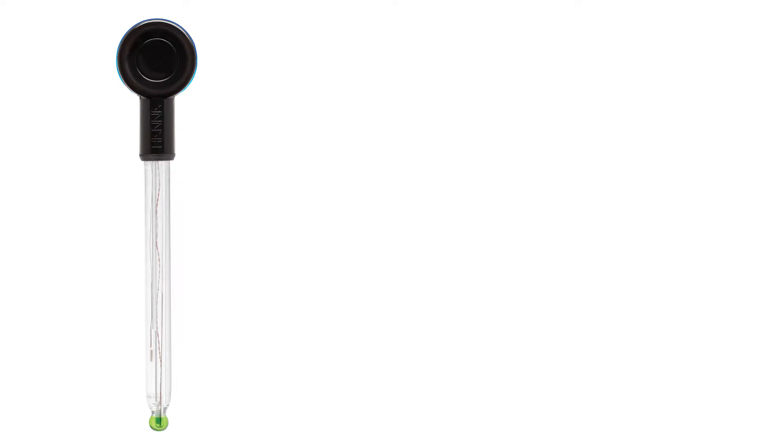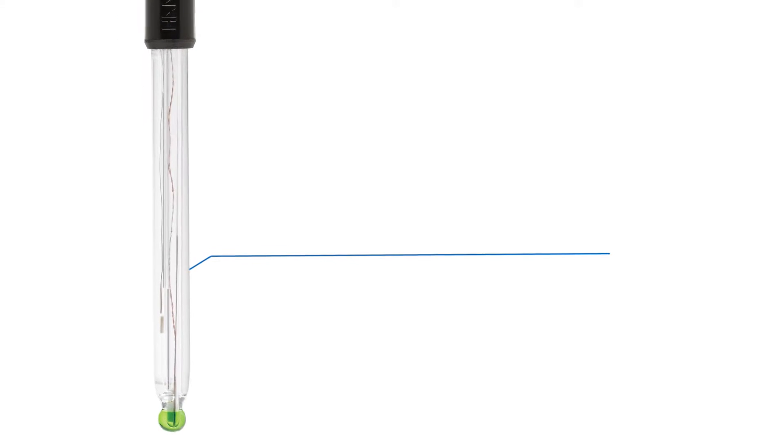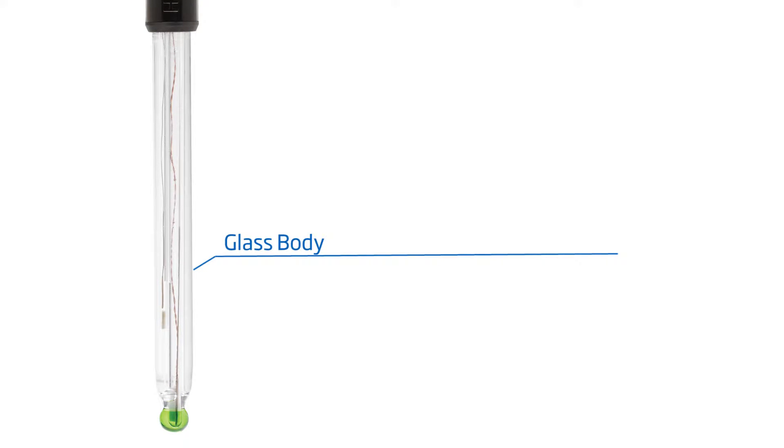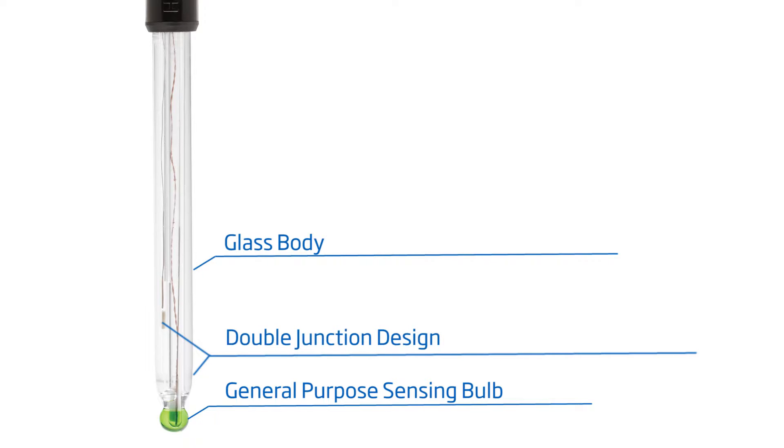This electrode is composed of a glass body and a spherical general purpose glass sensing bulb. The double junction design ensures that the gel electrolyte is free of silver chloride between the sample to be measured and the internal reference cell, resisting clogging and any potential precipitation at the junction.